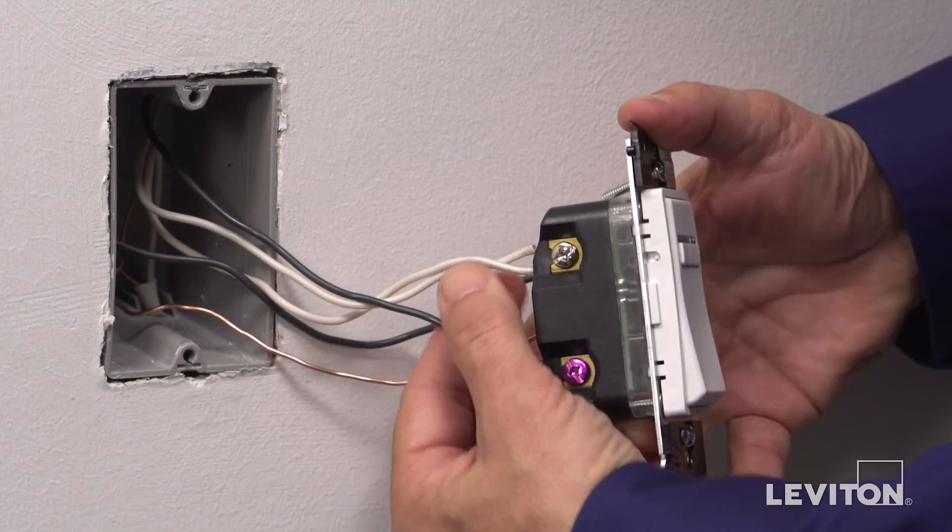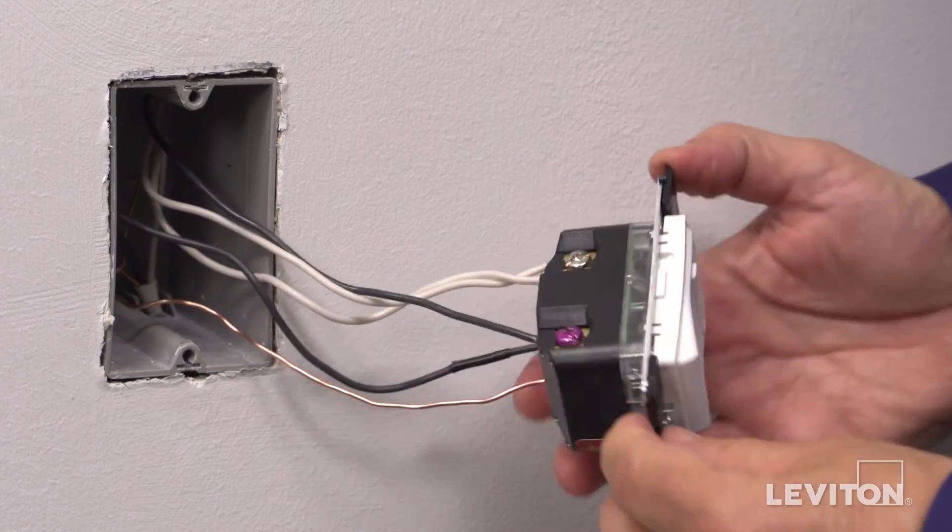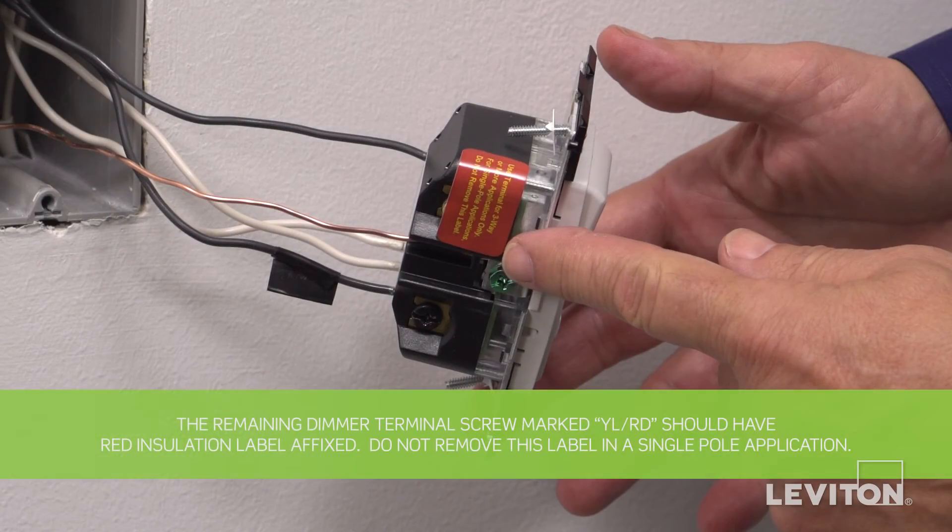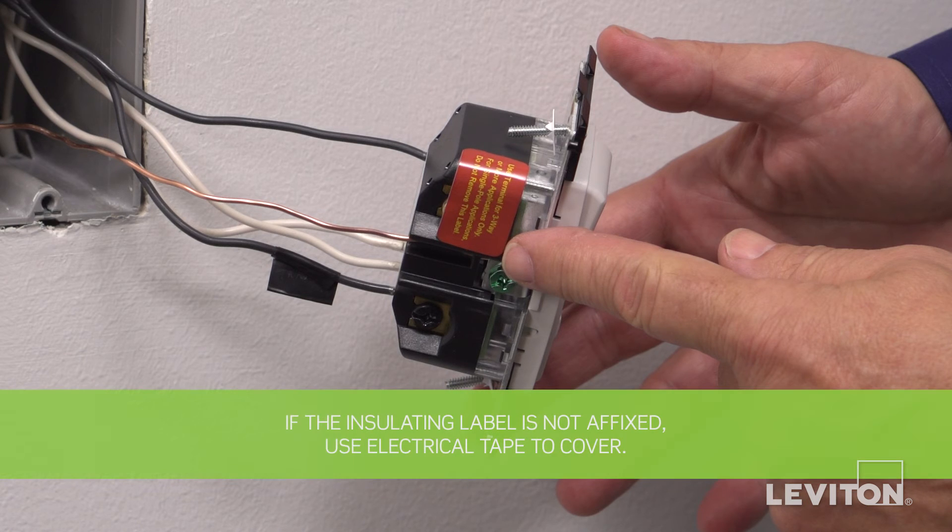Tug on all conductors to ensure termination is secure. Note, dimmer terminal screw marked YLRD should have red insulation label affixed. If insulating label is not affixed to terminal screw marked YLRD, use electrical tape to cover. The device is now terminated.